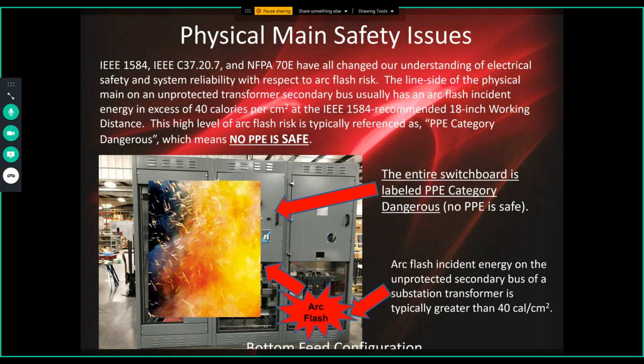So if you're working on the left-hand side of that I-Line section, replacing a breaker, and a tool from the previous maintenance outage falls between two faces of the primary bus, it could very well create an arc flash event and kill you, despite the main breaker being locked out. So there should only be one, I want to be clear, there should only be one arc flash label on the switchboard, and it better be labeled PPE category dangerous, saying no personal protective equipment is safe. Any questions at all?